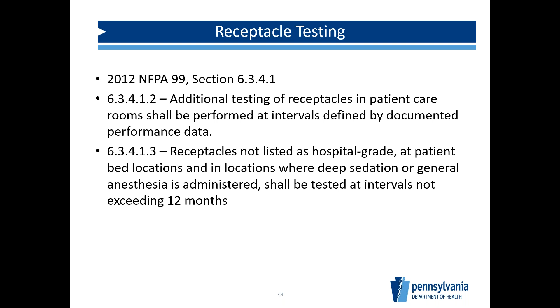So if somebody wants to talk about changing the interval from 12 months to a larger interval, that's something they want to work out with their field office, because what you're looking at here is documented performance data. I went out, checked them all, every receptacle worked, we didn't have any issues. I go back out 12 months later and I don't have any issues again. So next time I want to go out to 18 months. But you have to show that performance data, and you can't have any real failures, because then you're not demonstrating that you have the performance data.